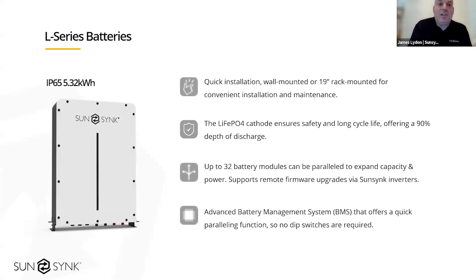Starting off with our L series battery. It's fully IP65 and it comes in a 5.32 kilowatt hour module. These are wall mounted or rack mounted as standard. They come with the wall mounted brackets in the box, but they also have the 19-inch rack ears on if you do want to put them in a rack.